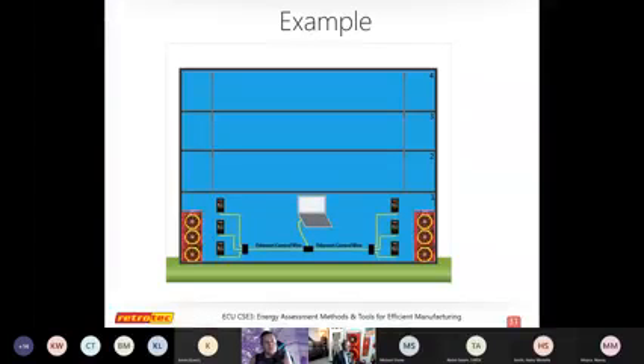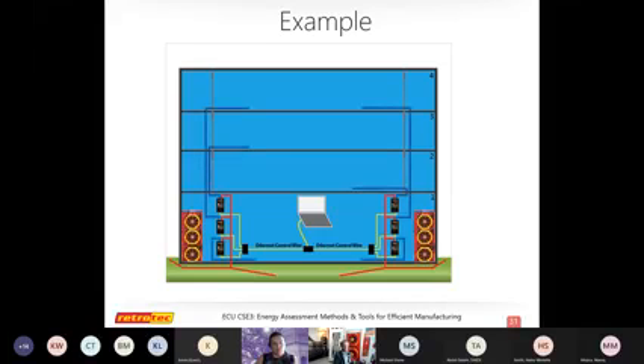And you run the fans with software on a PC, and you have all the digital manometers connected together that are talking to the software. So the laptop knows what each fan is doing, and then you have some tubing that references the outside. Again, this is a manometer that we're using, so it's just measuring pressure in one space versus another. So we have to have a reference place, which here is outdoors. And then we want to see what the pressure is doing to make sure that we're reaching that target pressure throughout the building. So we have other tubing. If we have multiple floors, we want to make sure that the entire building is getting under that pressure target.